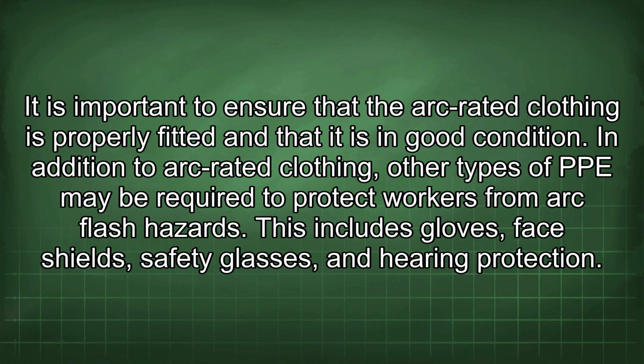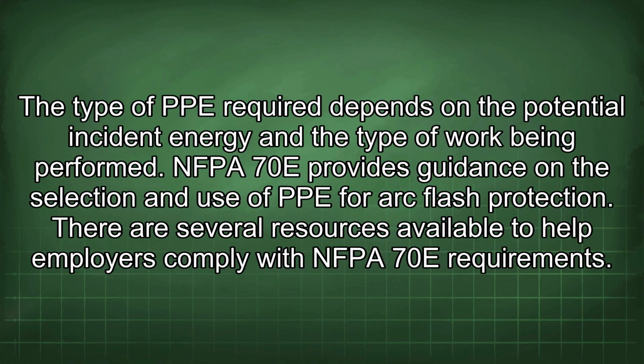In addition to arc-rated clothing, other types of PPE may be required to protect workers from arc flash hazards. This includes gloves, face shields, safety glasses, and hearing protection. The type of PPE required depends on the potential incident energy and the type of work being performed. NFPA 70E provides guidance on the selection and use of PPE for arc flash protection.